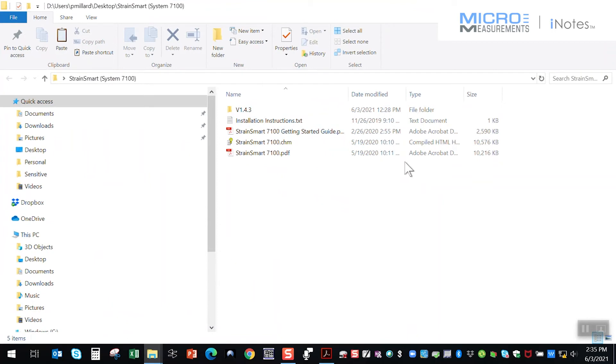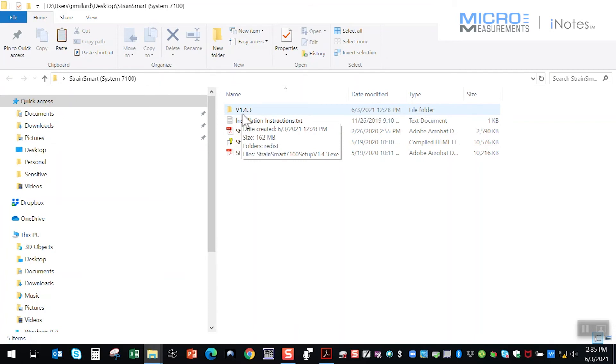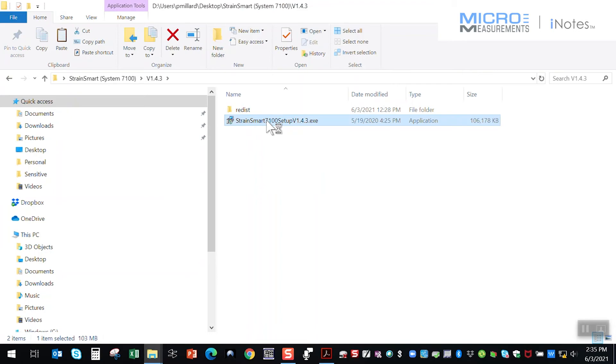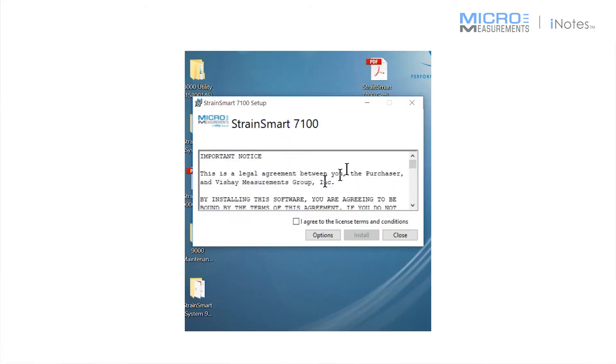So that last folder, which would be the last disk, another disk that you typically would receive from us. As of the shooting of this videotape, we've got version 1.4.3 for StrainSmart for the 7100. And there's an executable there that you just take a moment or two to fire it up and get it running. And it'll install the software. Now, one of the things that people often get held up by at this point is local permissions. So it might be a healthy practice to try to right click and run as an administrator both the installation and the StrainSmart software if you're not sure about just what level of permissions you've got locally on your PC.